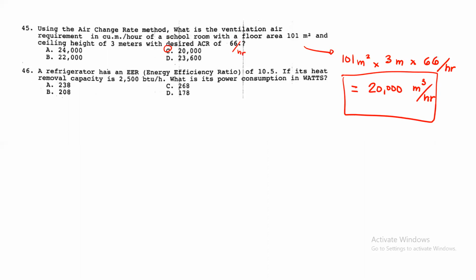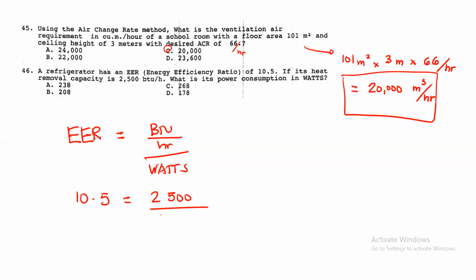So, next, 46. A refrigerator has an EER of 10.5. So, hinahanap na, meron tayong heat capacity in 2,500 BTU per hour. So, hinahanap yung power consumption in watts. So, EER natin is equals to, so BTU per hour per watts. So, ilan yung EER natin? 10.5. So, BTU per hour, 2,500 divided by power in watts. So, ilan yung power natin? So, the answer is, so, ang sagot dito, 238 watts in power.